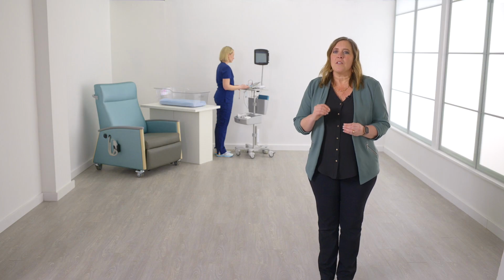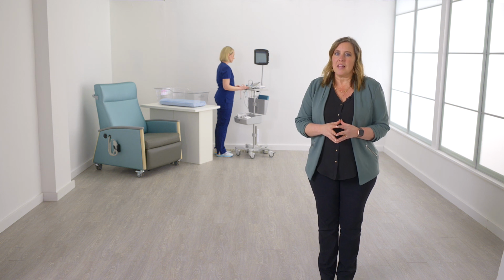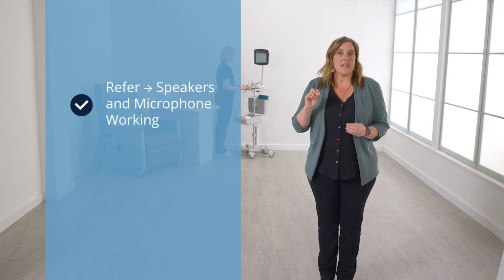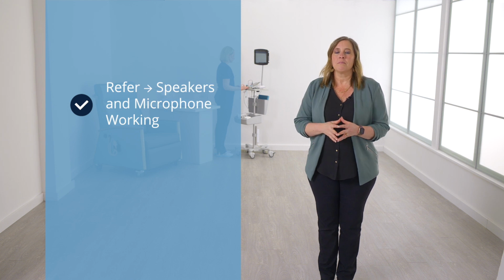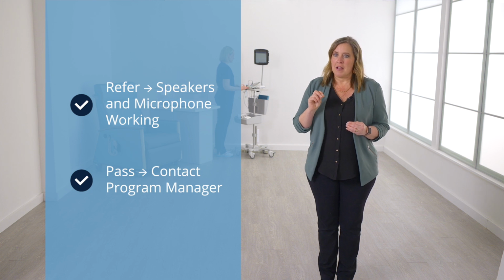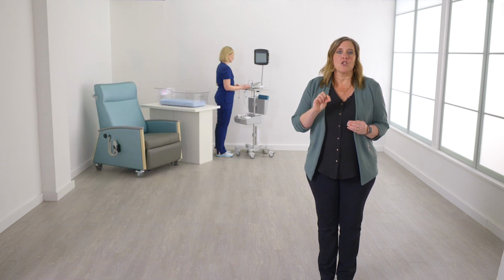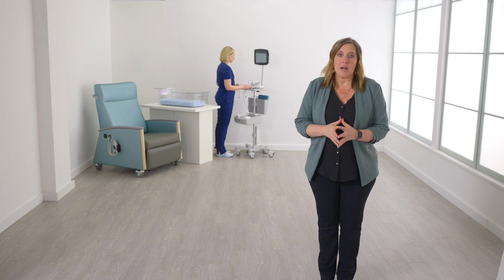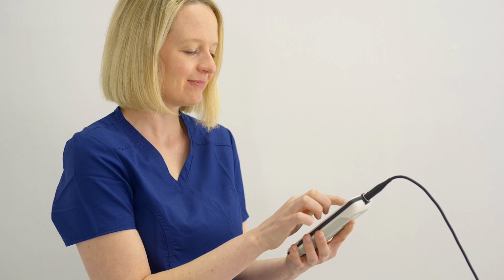Insert the probe with the ear tip into the infant ear simulator and perform an OAE screening. The probe fit or ear seal phase should proceed and the screening outcome should be a refer. While a refer result may seem counterintuitive, this quality check ensures that the speakers and the microphone in the probe are functioning properly. If the screening outcome is a pass, contact your program manager. A pass result should not be obtained because a present OAE can only be measured in a human ear canal.